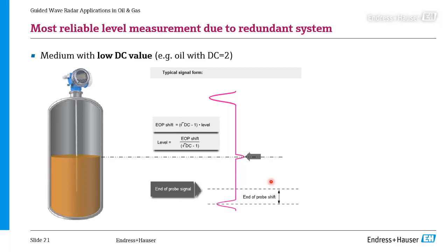Now, that also brings me to another point. If you get a small reflection back, that does not mean that the measurement itself is inaccurate. In general, if you get a small reflection back, whether it's on guided wave radar or on a free space radar, it is accurate. The amplitude of the signal itself is nice to have because it makes the signal more reliable and available, but it does not have to say anything about the accuracy of the level measurement itself. So please do not make the mistake of thinking big amplitudes mean high accuracy. That's not the case. Small reflections can have the same accuracy, or maybe even better. Who knows?